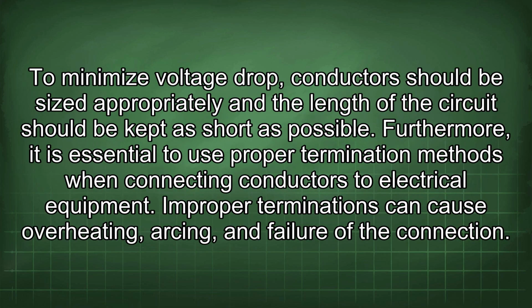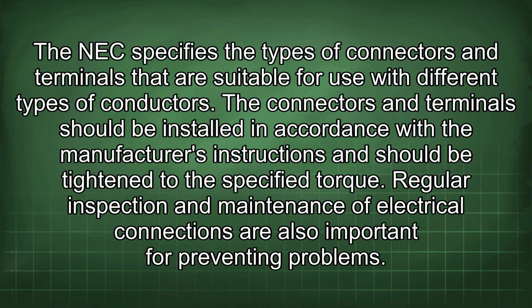To minimize voltage drop, conductors should be sized appropriately and the length of the circuit should be kept as short as possible. Furthermore, it is essential to use proper termination methods when connecting conductors to electrical equipment. Improper terminations can cause overheating, arcing, and failure of the connection. The NEC specifies the types of connectors and terminals that are suitable for use with different types of conductors.